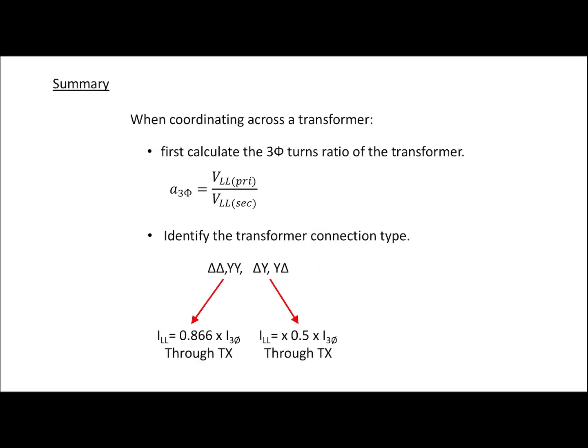In summary, when coordinating across the transformer, first calculate the three-phase turns ratio a_3φ, then identify the transformer connection type. If it's Delta-Delta or YY, the factor used to calculate the line-to-line current is 0.866 times the three-phase current. If the transformer is Delta-Y or Y-Delta, use a factor of 0.5 times the three-phase current to calculate the line-to-line current when going through the transformer.